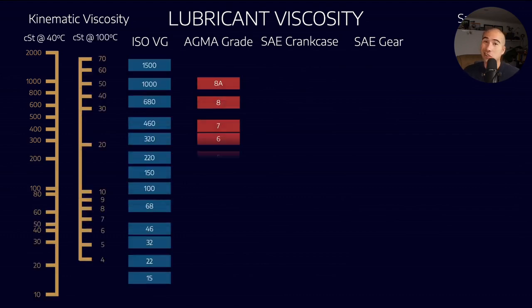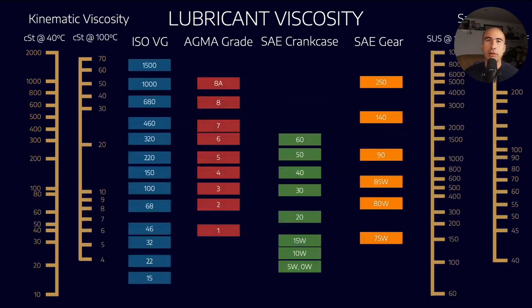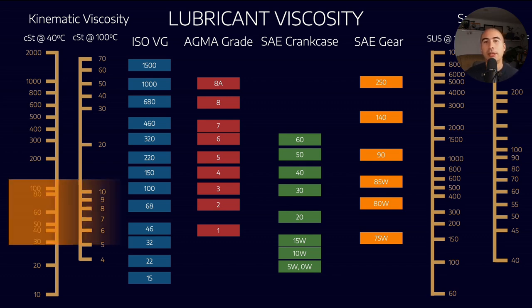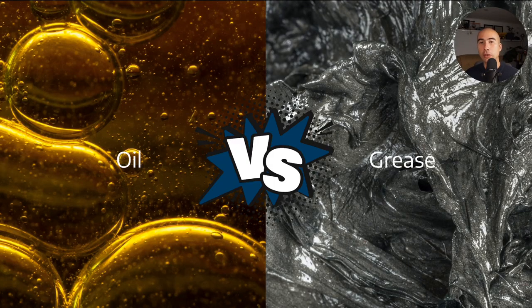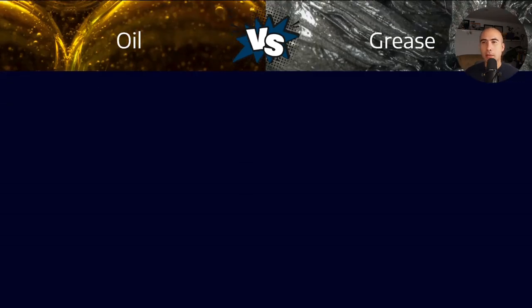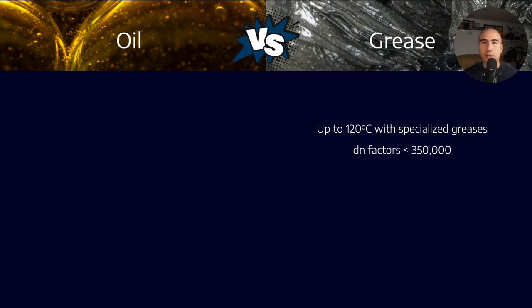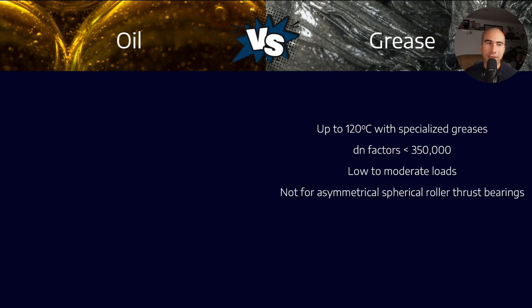In practice, the OEM will probably define what lubricant viscosity to use. It's rare unless you're in the design phase that you'd define it. Typical viscosity for rolling element bearings is between 32 and 100 most of the time. Next, determine whether to lubricate with oil or grease. With grease, we can go up to 120 degrees Celsius with specialized greases. DN factors are typically limited to 350,000. Grease is used for low to moderate loads like electric motor bearings.